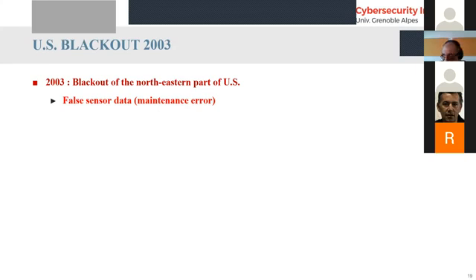He changed the sensor. Now, in electrical networks there are two standardized categories of sensors: one with an output between 0 and 1 ampere, and another with an output between 0 and 5 amperes. Both are supported by all PLCs and protection relays used in electrical distribution worldwide. You just have to configure the relay to match the sensor's output range.